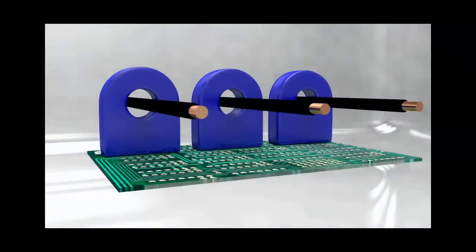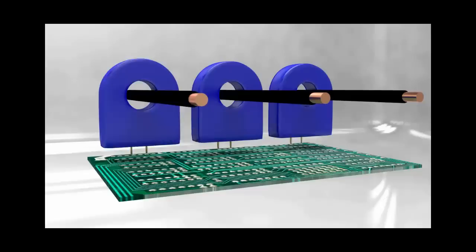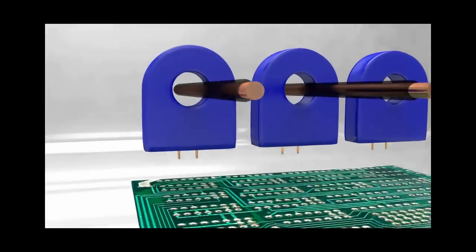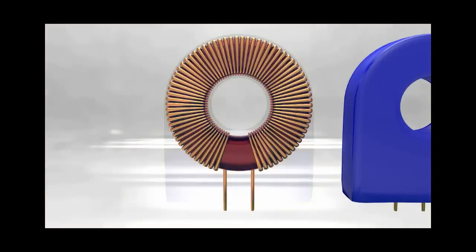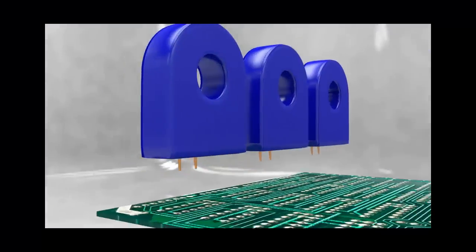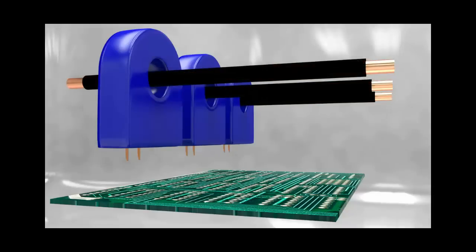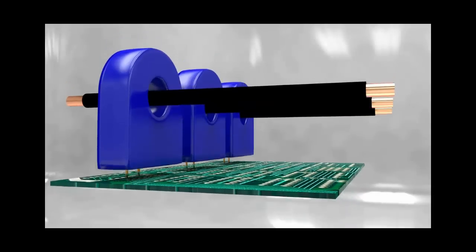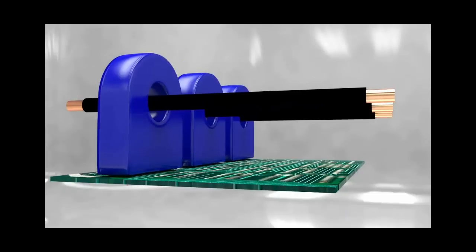Here's the inside of a solid state overload relay. We have the three CTs or current transformers, which is essentially a wire wrapped around a donut shaped piece of metal. The motor current travels through the donut, which creates a magnetic field that produces a much smaller current through the CT wire, which is then connected to a circuit board where the signal is processed.